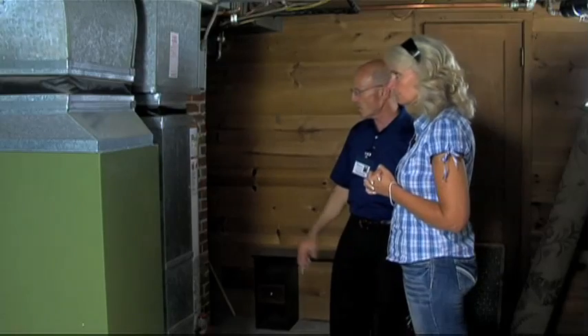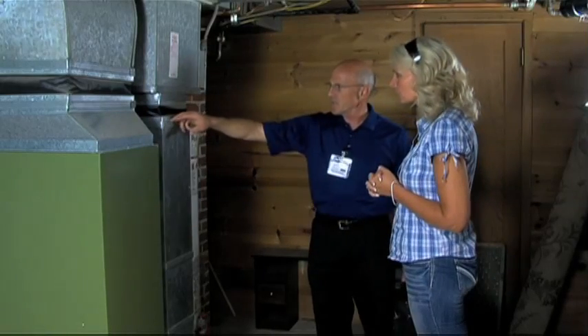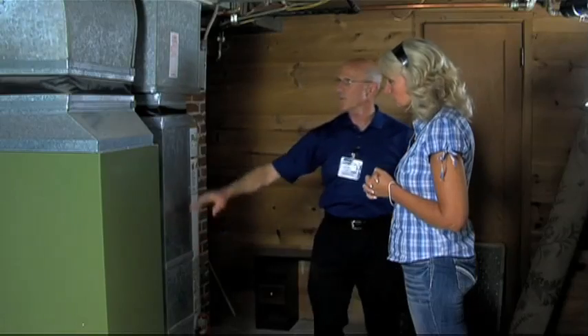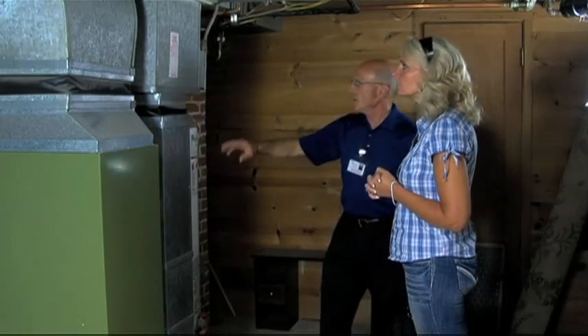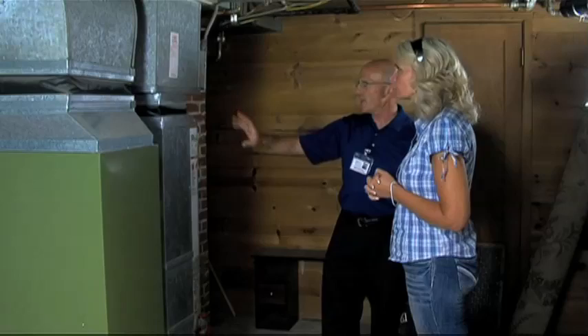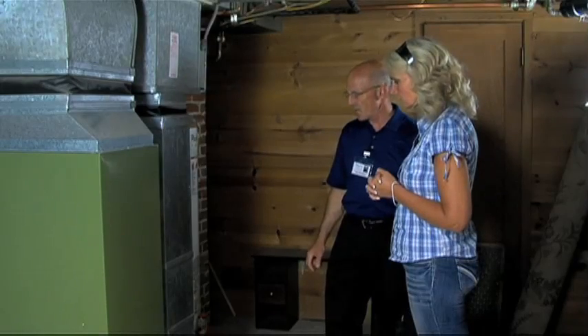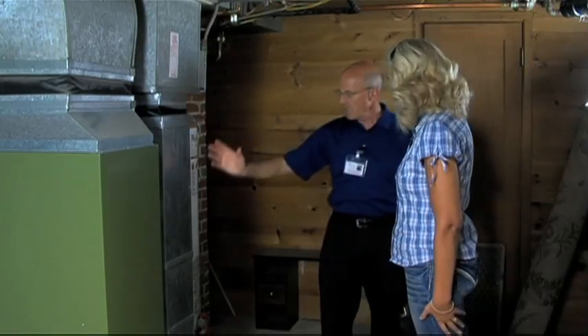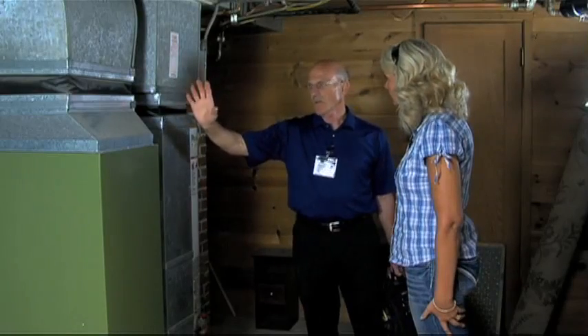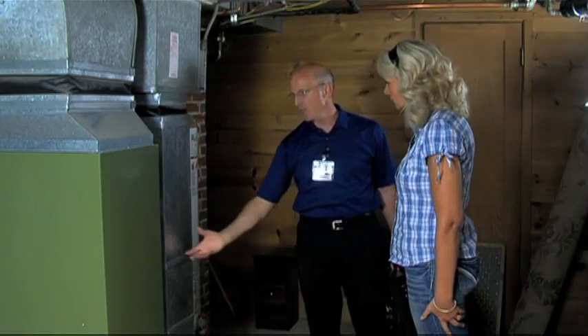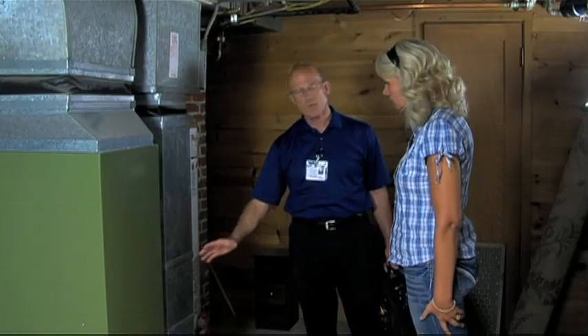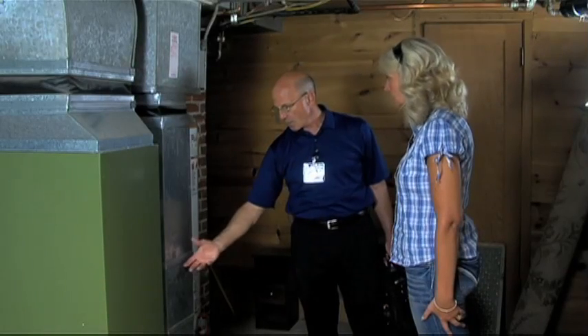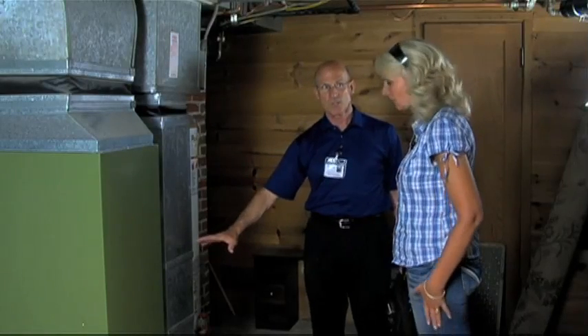Okay, so this is good craftsmanship too. These types of connections are not airtight the way that this type would be. And that's always a question mark, because the air coming back is usually a little less than the air going out, and that creates a vacuum here. And so when the system is running, air will be pulled into this ductwork from the basement area. So whatever's in the basement, damp or whatever, gets pulled into your ductwork, just so you know.